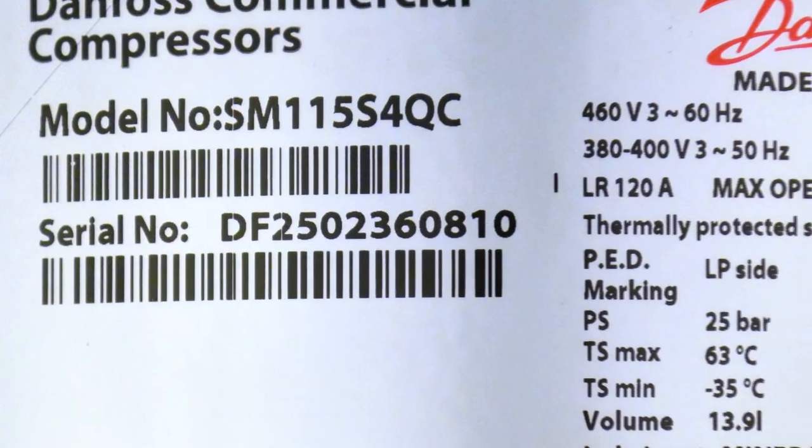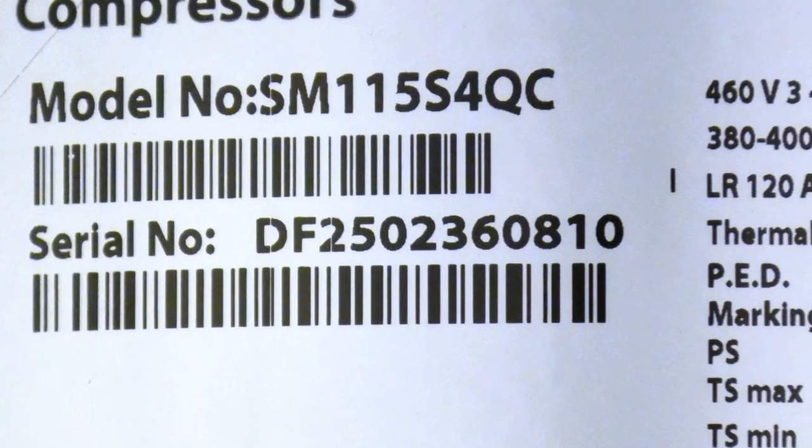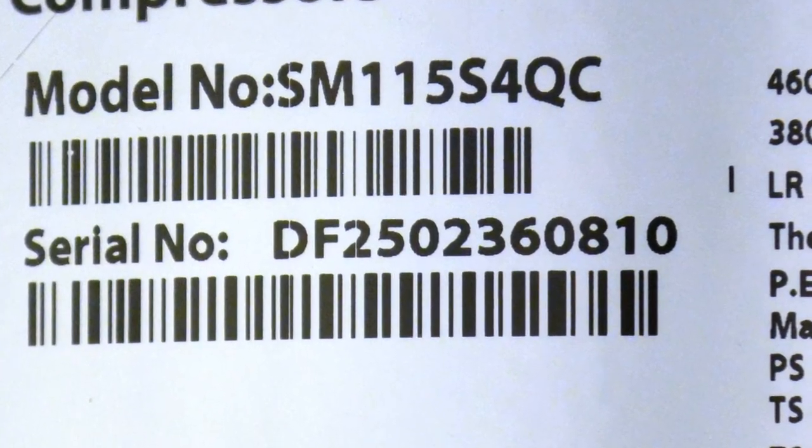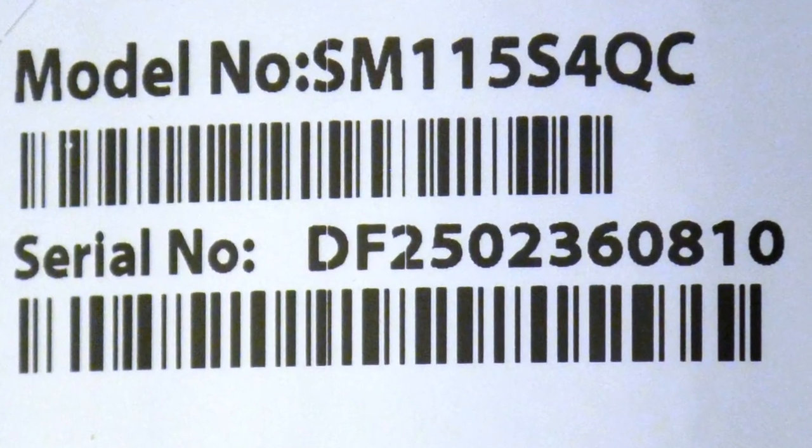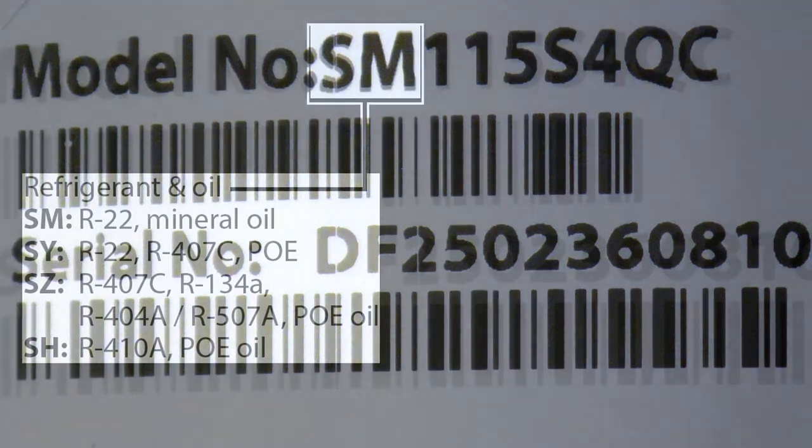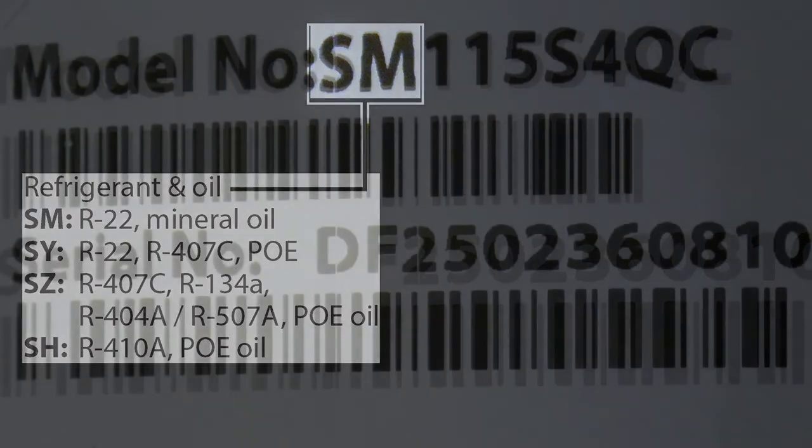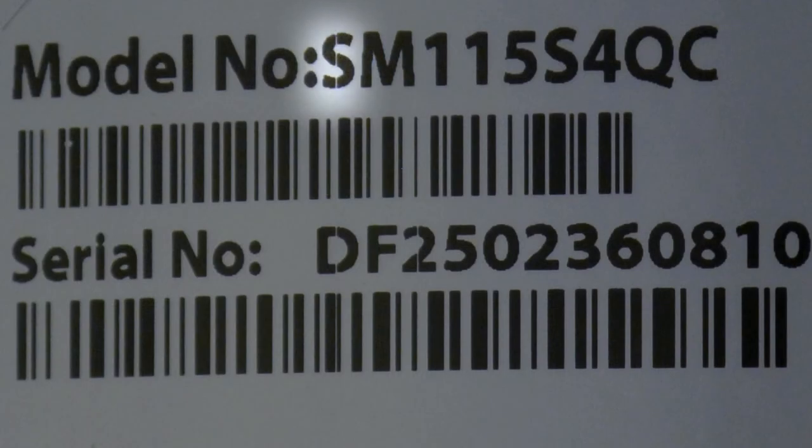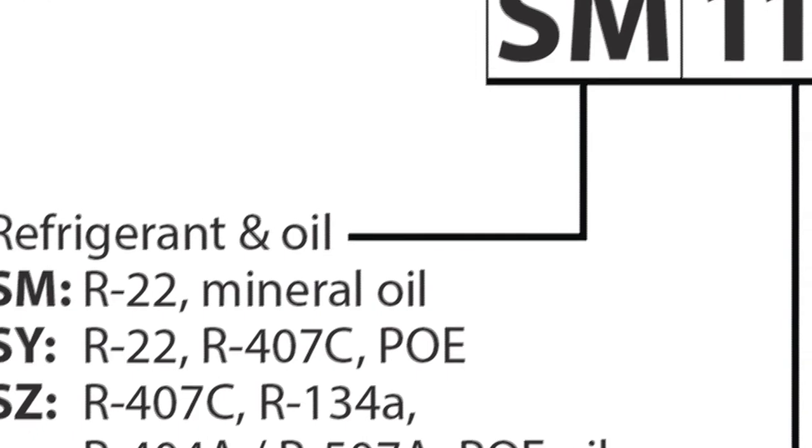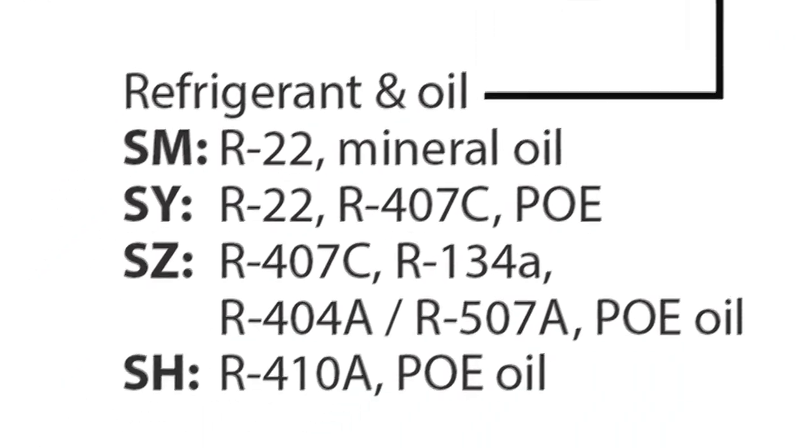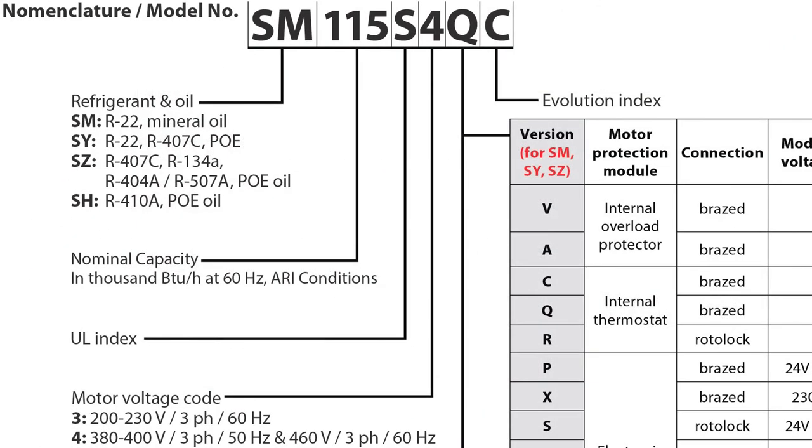To begin, here is an example of the nomenclature used for the S-Series compressors. The first two digits of the nomenclature signify the product family, as well as the refrigerant and compatible lubricant that the compressor uses. The first digit, in this case S, signifies a scroll compressor used in commercial and large commercial applications. The second digit signifies what refrigerants and lubricants with which the compressor is compatible.